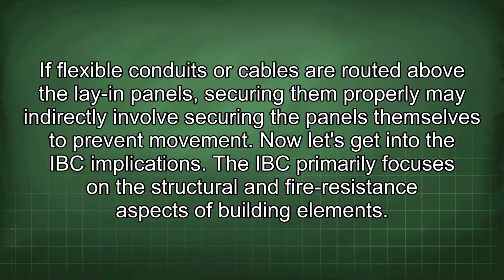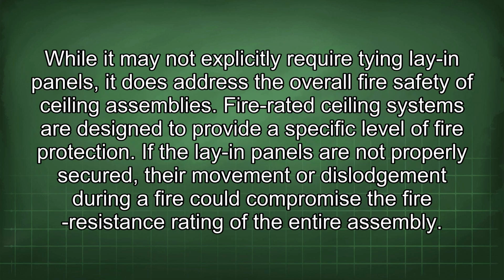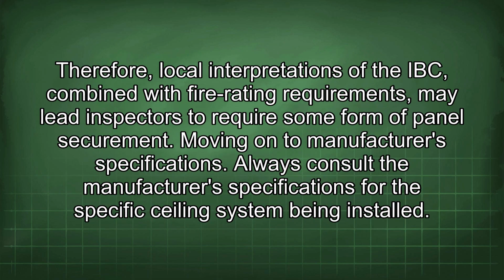The IBC primarily focuses on the structural and fire resistance aspects of building elements. While it may not explicitly require tying lay-in panels, it does address the overall fire safety of ceiling assemblies. Fire-rated ceiling systems are designed to provide a specific level of fire protection. If the lay-in panels are not properly secured, their movement or dislodgement during a fire could compromise the fire resistance rating of the entire assembly. Therefore, local interpretations of the IBC combined with fire rating requirements may lead inspectors to require some form of panel securement. Moving on to manufacturer specifications.